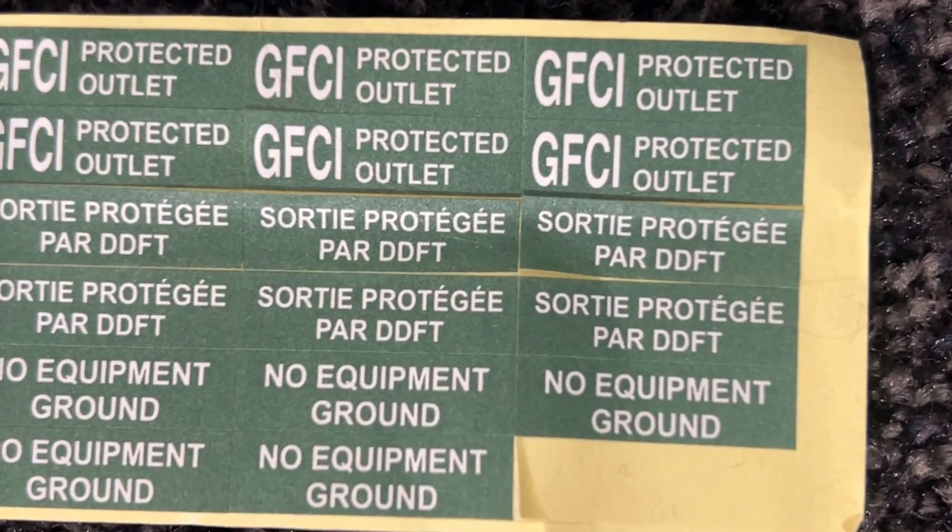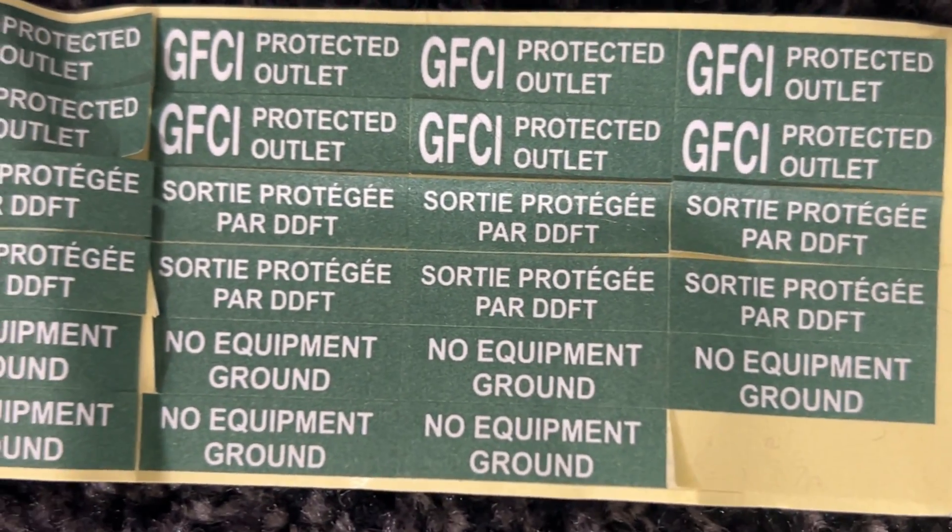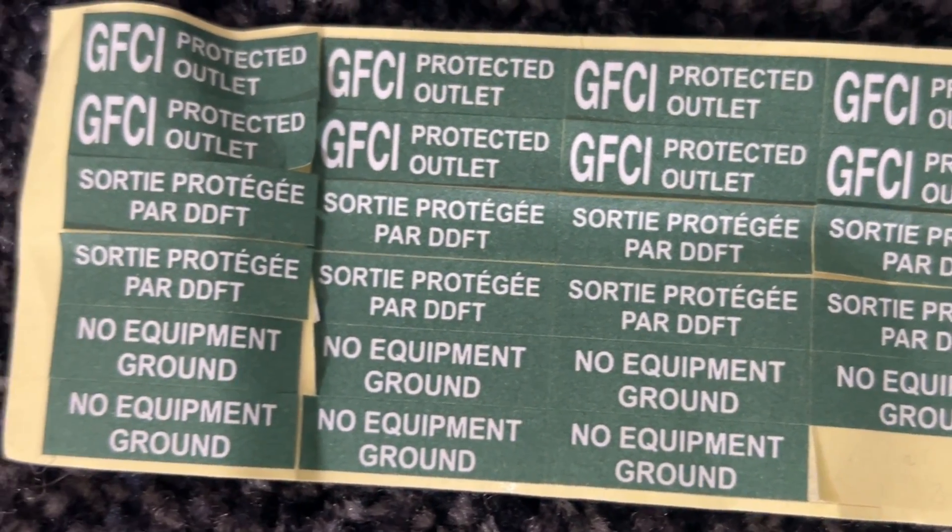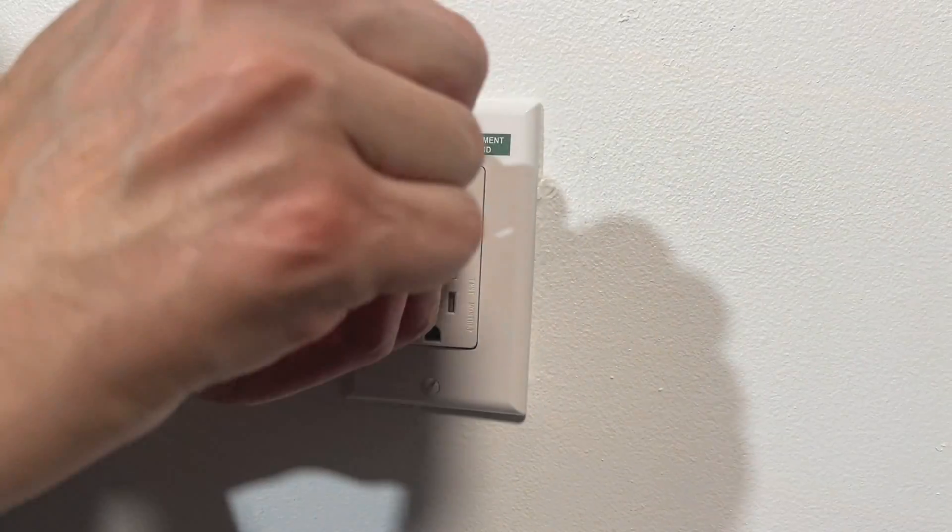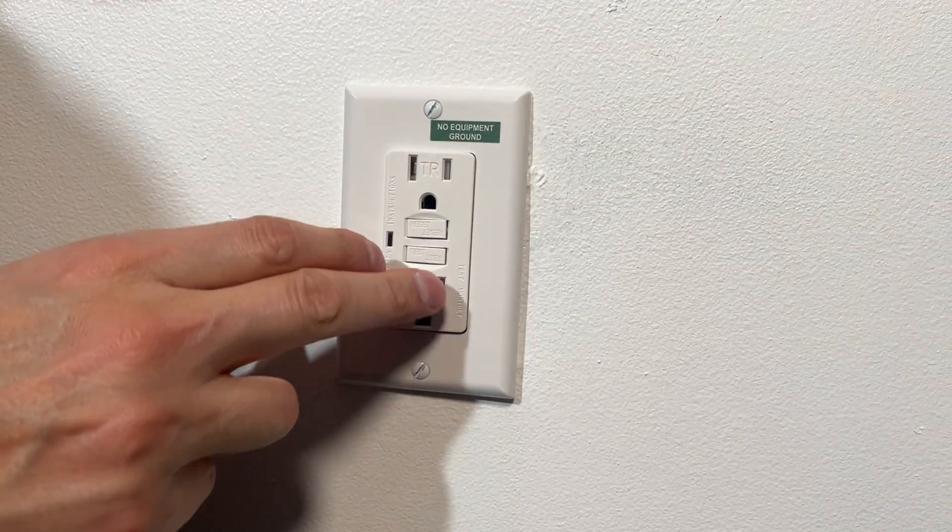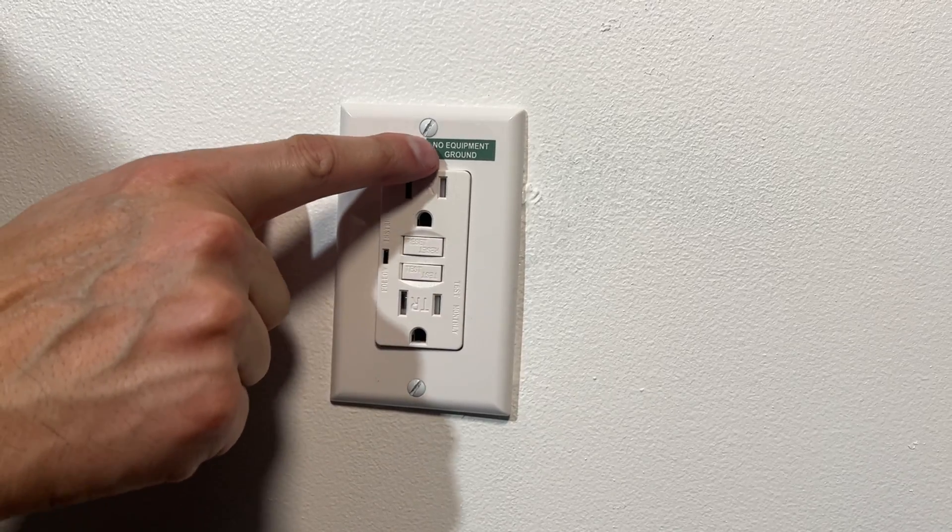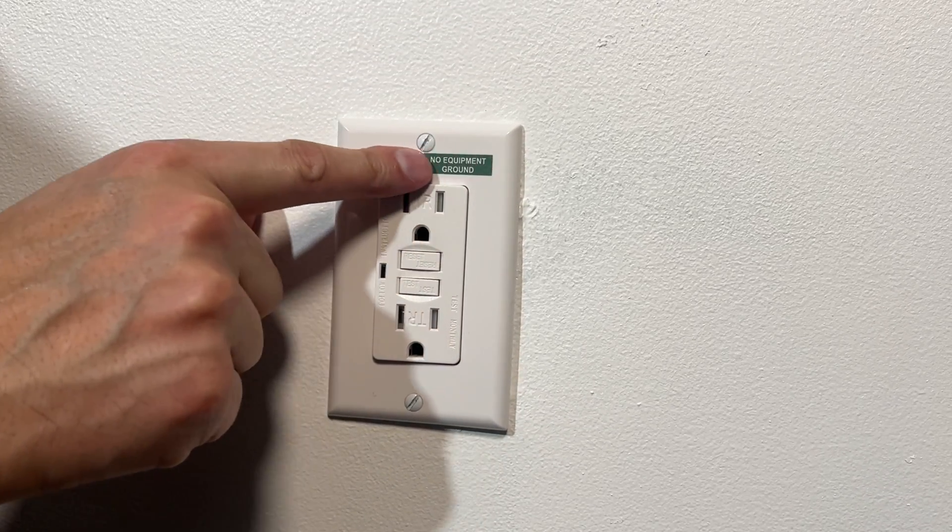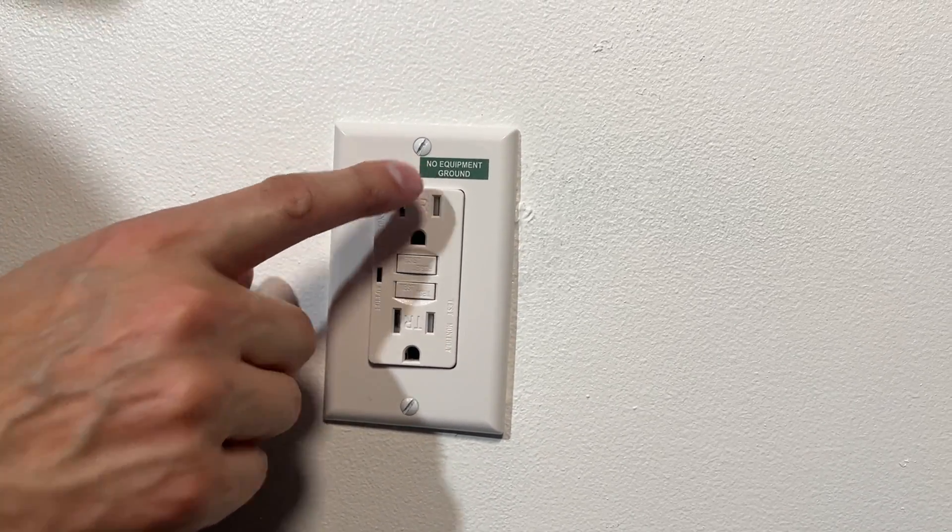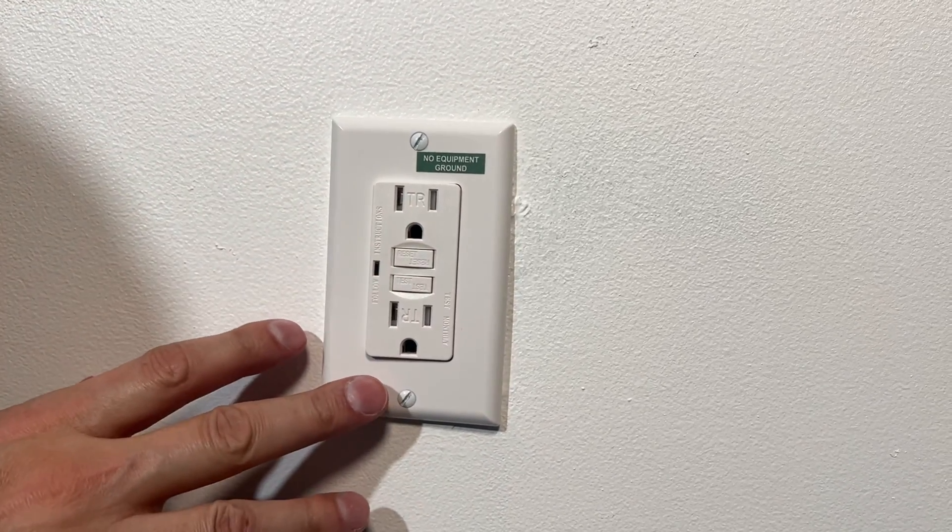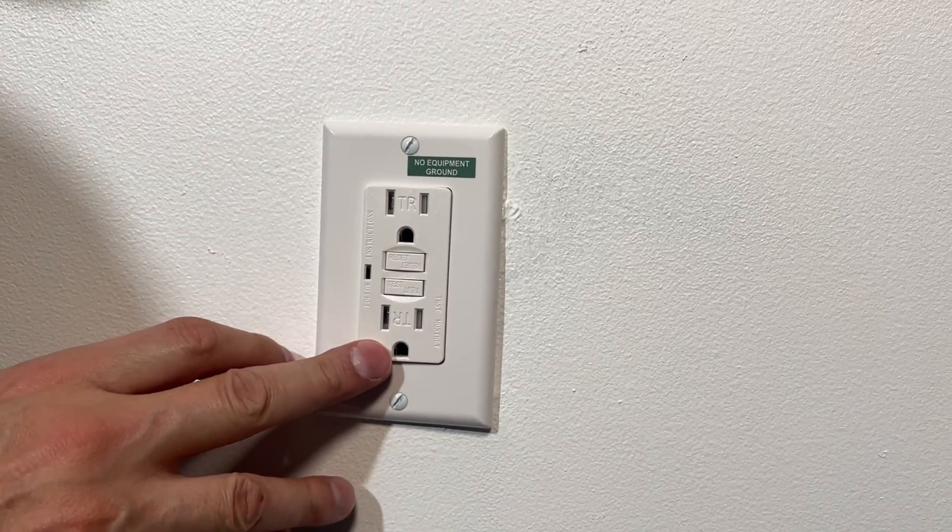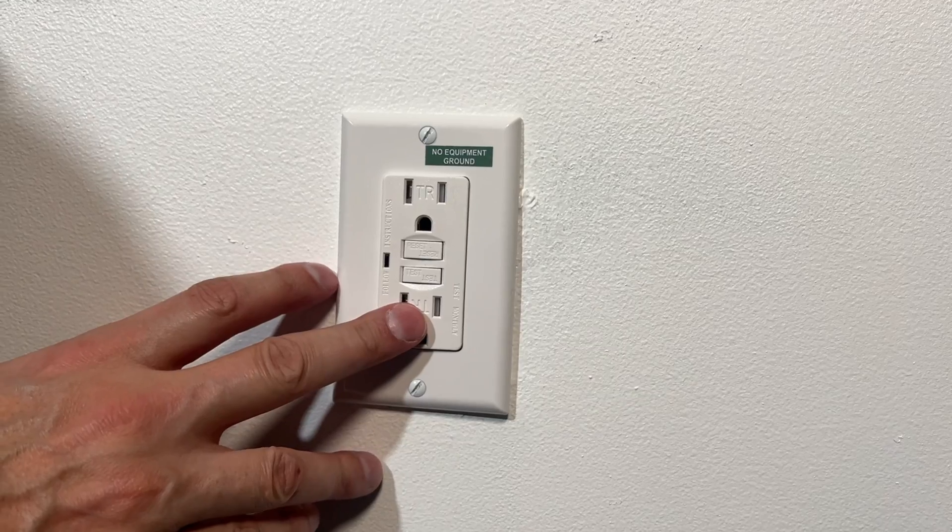So in this case, the correct sticker reads no equipment ground. Even though we have a safety outlet here, we still have to label it as no equipment ground. So everybody that looks at the three prong outlet won't be deceived.